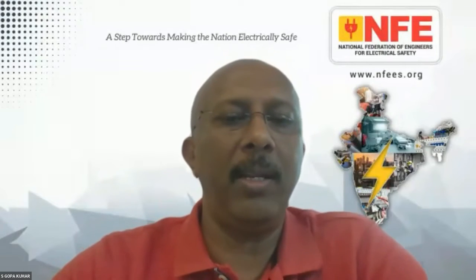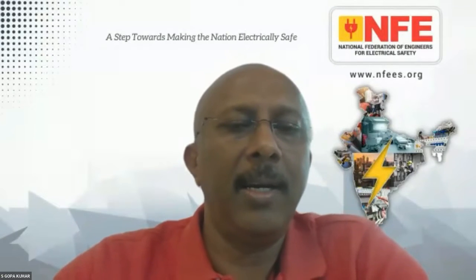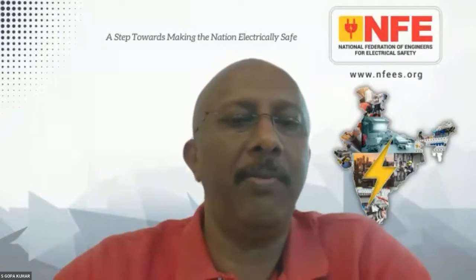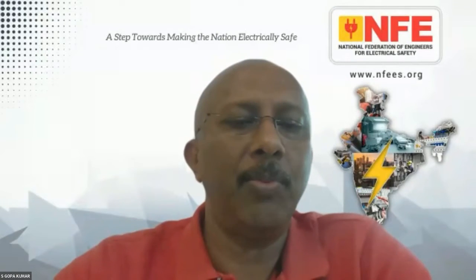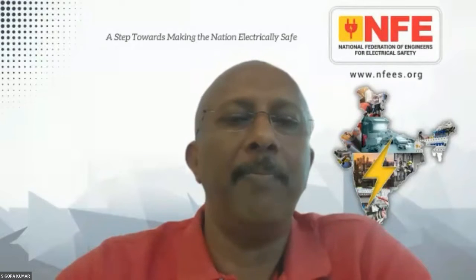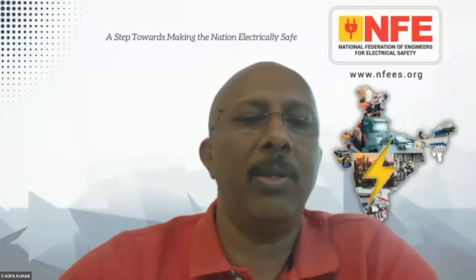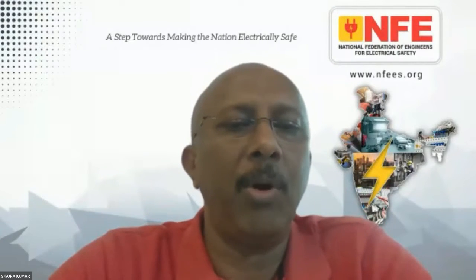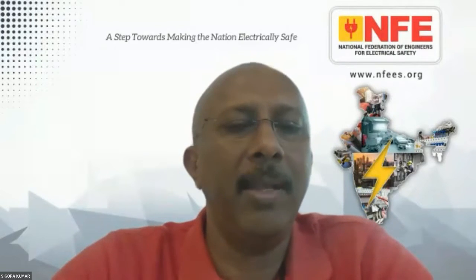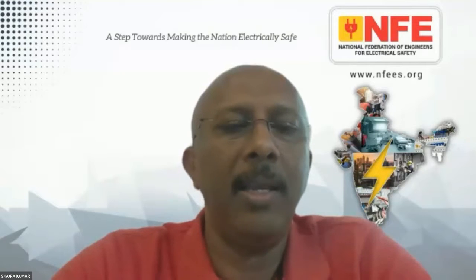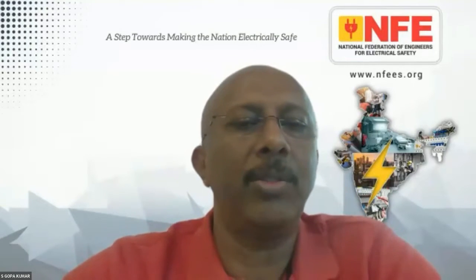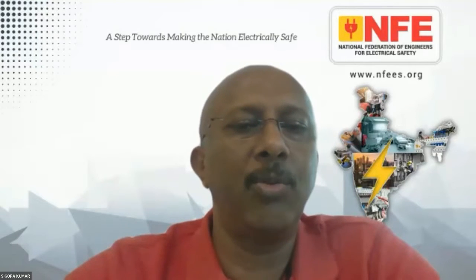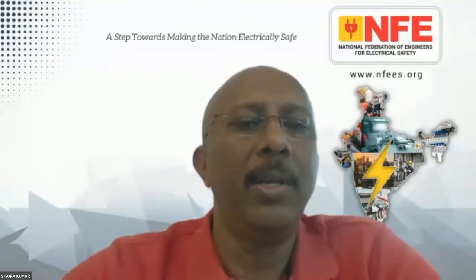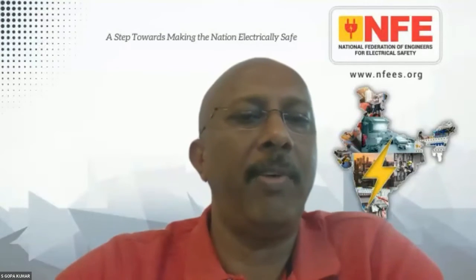Okay, the fire detection and suppression systems are specified. But if we look at the NEC, the requirement at the DC side, DC arcing is highly dangerous and it can create continuous fire, which will spoil the whole installation, the whole building if it is a rooftop. For avoiding DC arcing, especially on solar PV, double insulation is made mandatory; you cannot compromise on double insulation. But in most of our solar PV installations, especially inside the combiner box, double insulation measures are compromised. That is the reason most fires in solar PV are in the combiner box, because double insulation is missing. Also, sometimes people use normal wires with single insulation for this application. These are actually violations. So the first thing is you should comply with the standards, not only provide the fire detection and suppression system.